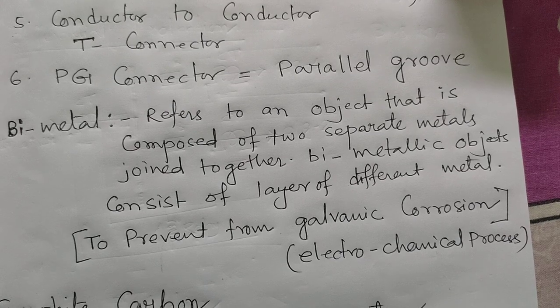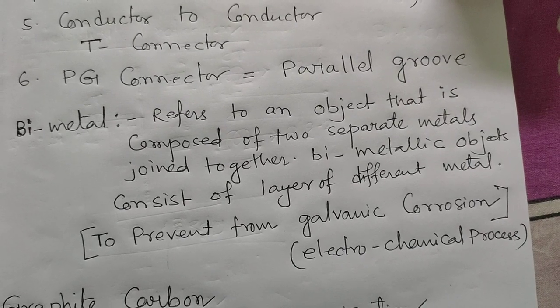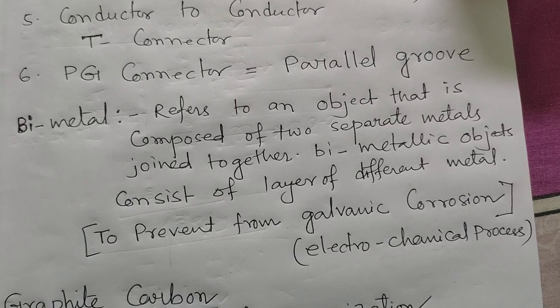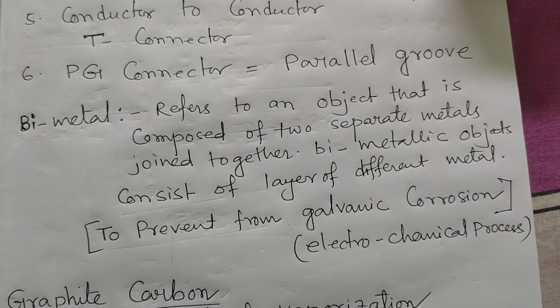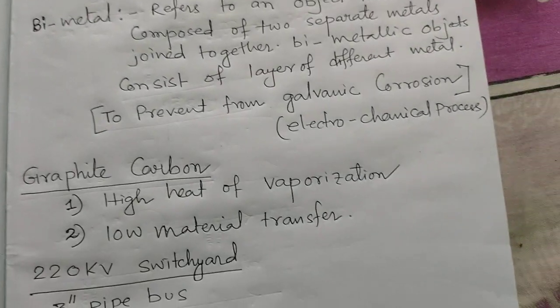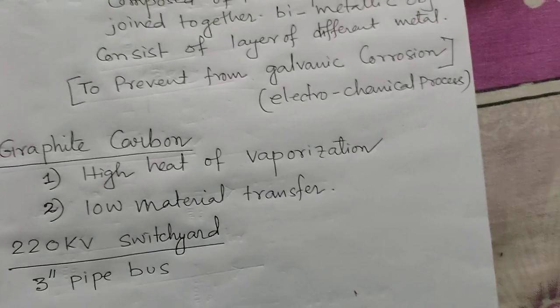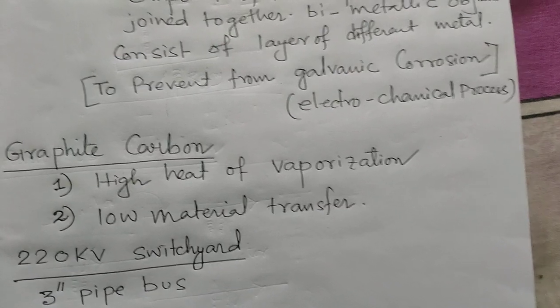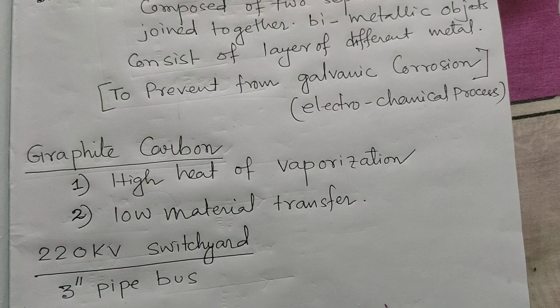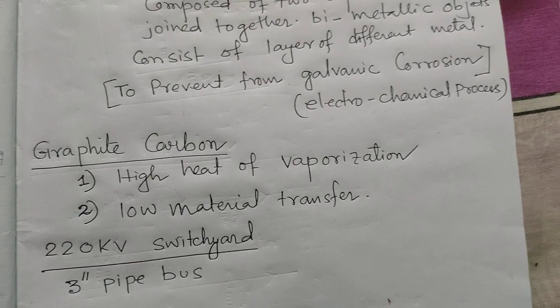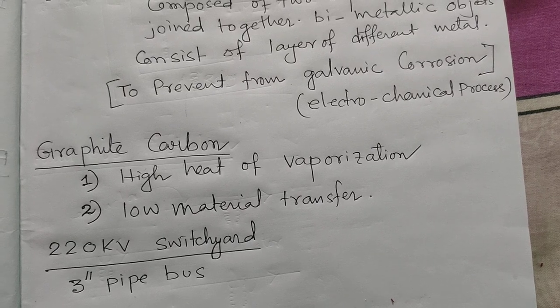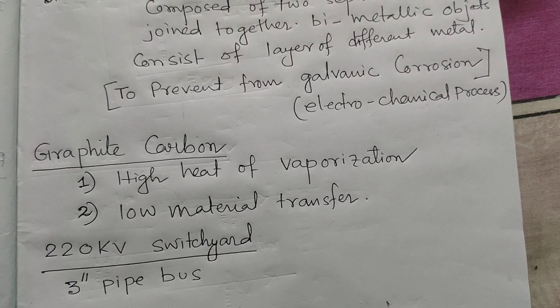We use bimetals between the copper stud of the substation and the aluminium connectors. We have attached some pictures related to the clamp connectors — how they are being used at substations, at substation studs, isolator studs, and pipe-to-pipe connectors. Graphite carbons are being used nowadays to strengthen the systems.